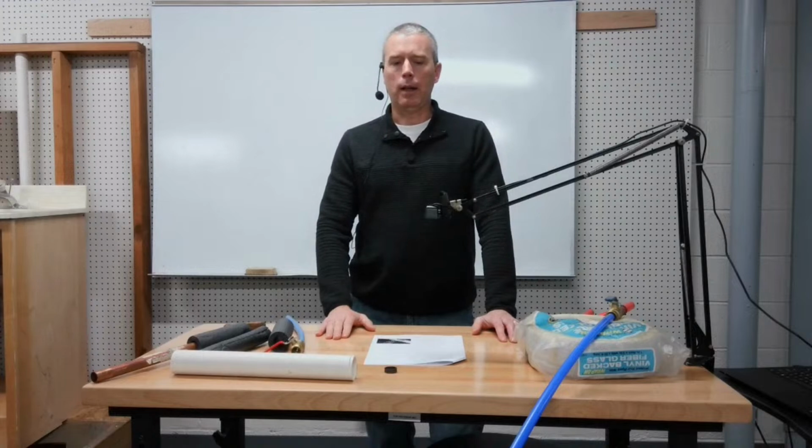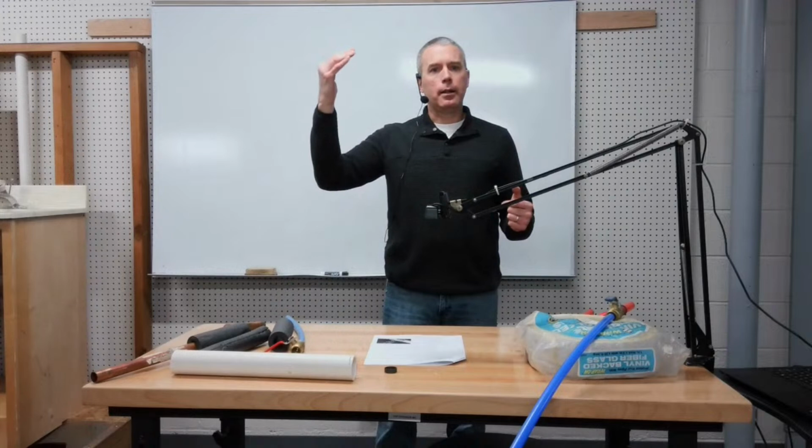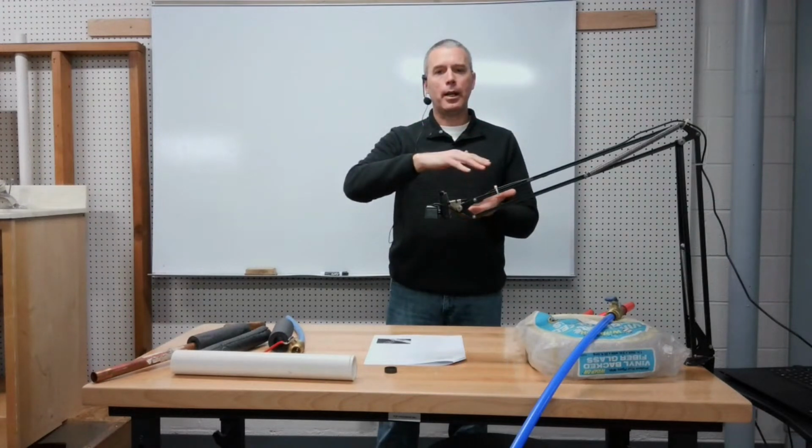Yeah, so I know it's been in the news the last few years about like Texas, the super cold weather that they've got. They are just not set up for cold weather. A lot of their water lines run in the attic. They'll be on slab, so there's no basement. So when that water line comes in and runs across the attic, it's insulated, but there they insulate for heat. So there's a good chance that the water lines are on top of the insulation. So it's water lines, insulation, and then the ceiling of your house. So when they get inclement weather like they did, they're not dialed in for that. So that's something I've run into a few times.